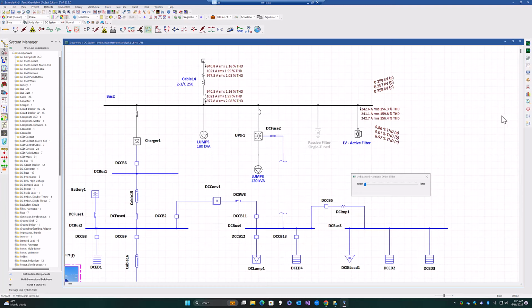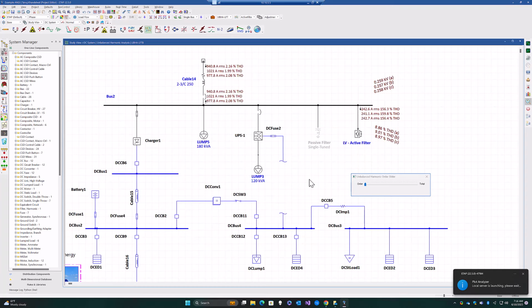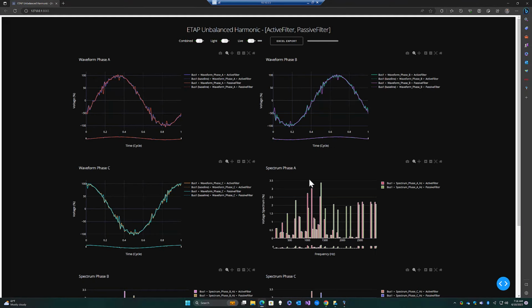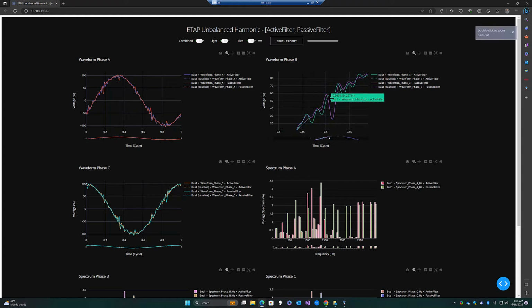But first, before we do that, let me bring up the plot analyzer. Here we can compare our active and passive filter for, let's say, bus number 1, which is a bus upstream from bus 2. We can compare our phase A, B, and C phases in terms of waveforms and spectrums. And of course, we saw our unbalanced vector visualizer, so you have an idea now between the time domain and frequency domain. Here we can see, for example, phase B as an example. We can zoom in here. We can see the baseline as well as the actual waveforms. Let me take the baseline out, and you can compare the active filter response versus the passive filter response.